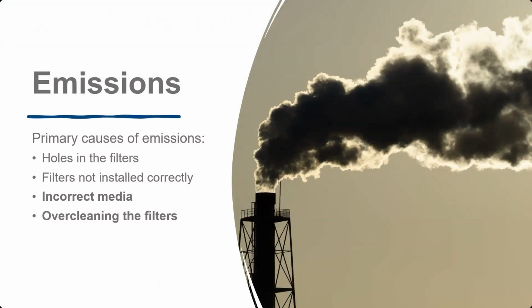And so emissions, I touched on that a little bit. We already talked about the primary causes of emissions. Holes in filters, lots of times that's from abrasion. Filters not installed correctly. I'm not going to really dig into that one because there are so many types of filters. We'd spend too much time on it, but it's very important to make sure that you're properly installing your filters. I've seen a lot of funny stories over the years.